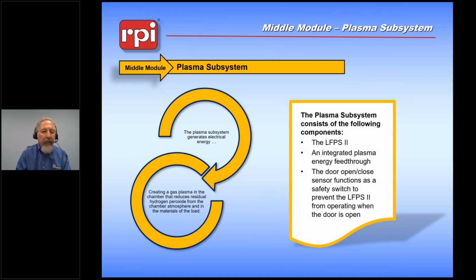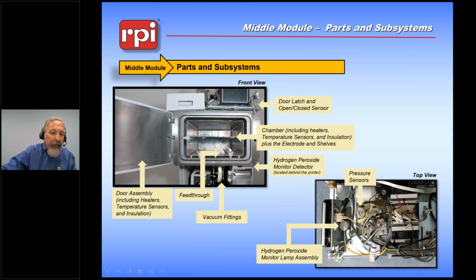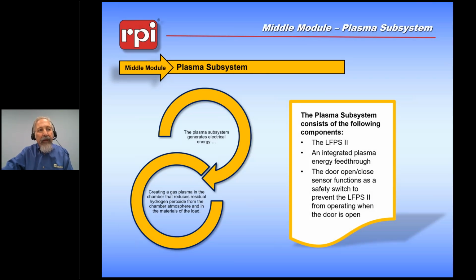Okay, the plasma subsystem. So once the hydrogen peroxide has been concentrated and has been released into the chamber and has been allowed to flow into the various lumen, hinges, and very fine places within the material in the chamber, we then turn on a low frequency power supply, and that low frequency power supply generates a plasma because it's flowing between this surface and the chamber wall, and that allows that plasma to develop, and that plasma will spread through the entire contents of the chamber, through all the hydrogen peroxide, getting into all of the lumen, getting into all of the hinges, getting into every spot that it needs to.